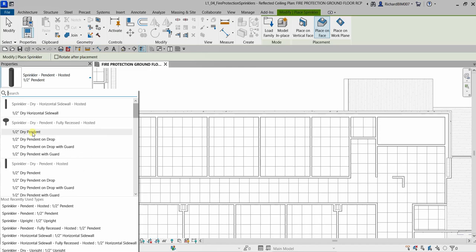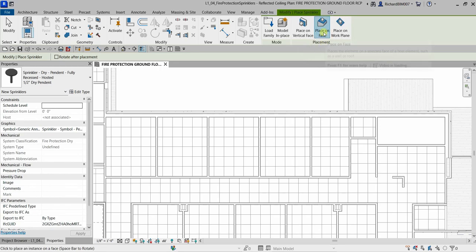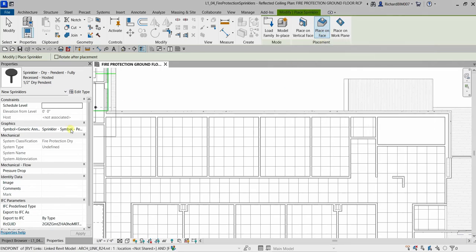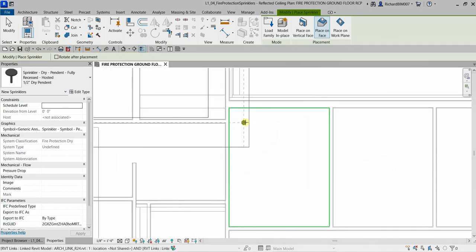From the type selector, we will use the option 'Place on Face.' We do not need to specify the elevation here because it is understood that we are placing it on our ceiling. The ceiling height was already specified when you created it, so there's no need to manually set the sprinkler height.